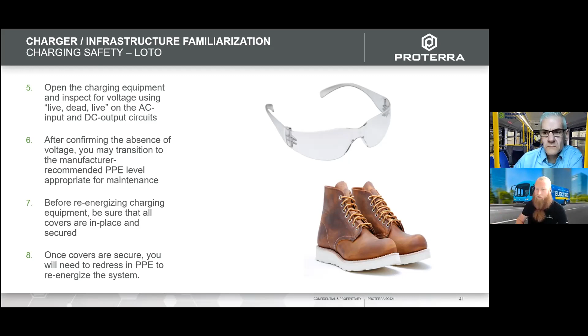Before re-energizing, make sure all the covers are closed and everything is locked down, back in normal working order. Just before you re-energize, make sure you have all of your PPE on again, to ensure there are no potential arc flash hazard events as you re-energize.